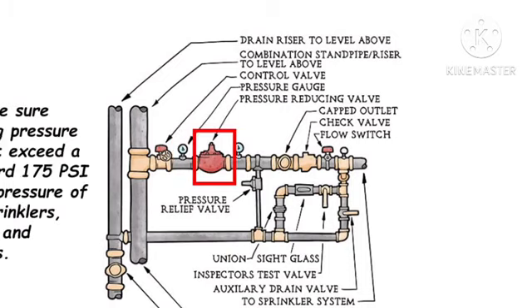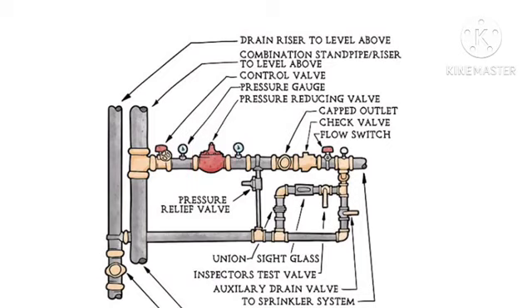Pressure reducing valve. Provided to reduce the system pressure such that the working pressure will not exceed the standard 175 psi listed pressure of the sprinklers, piping, and fittings. PRVs can also be used to limit the system pressure to higher amounts when pressures are allowed to exceed 175 psi. Control valve for the entire riser is required to permit isolating a riser without interrupting other systems. Size of minimum 4 inch, unless hydraulically calculated to permit a smaller size.